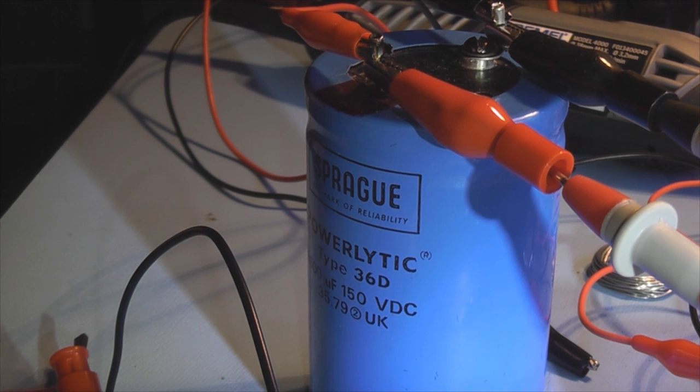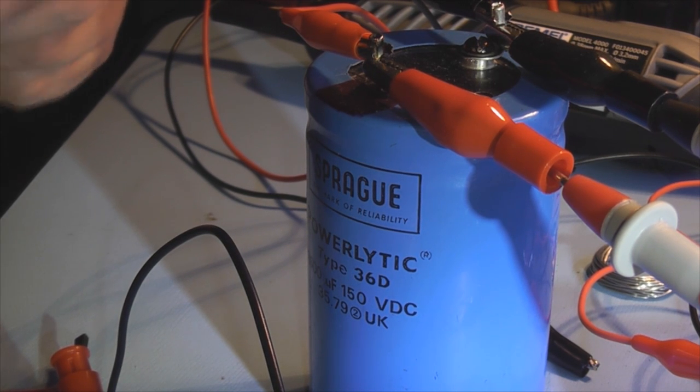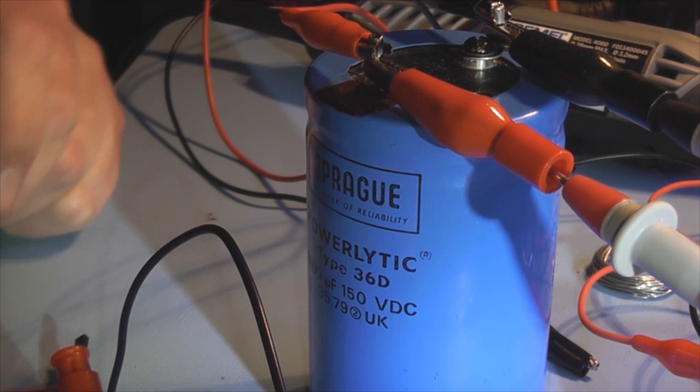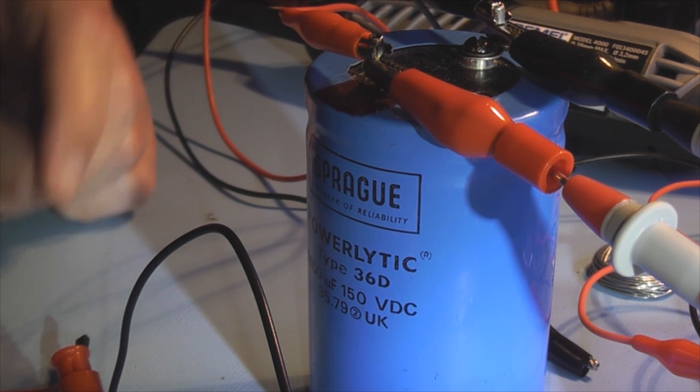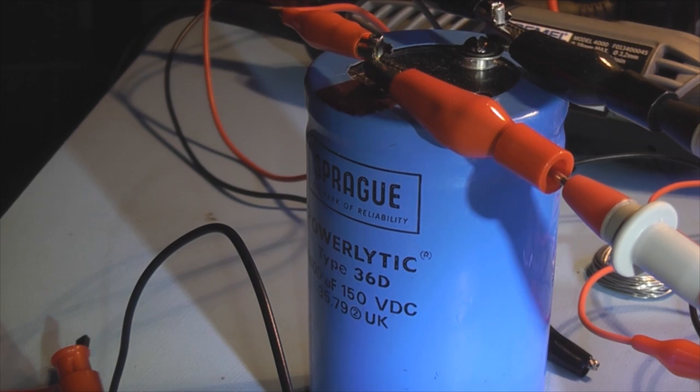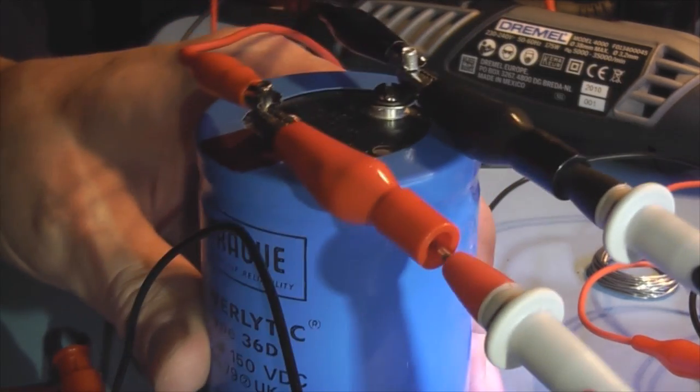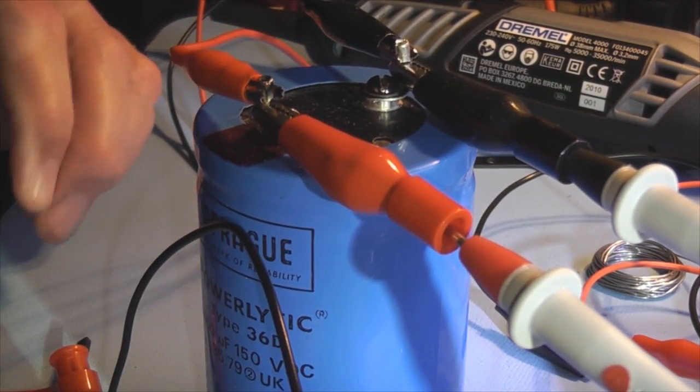Which in turn will cause less internal stress in the capacitor. Because a lot of capacitor damage is caused by the capacitor banks and things being arced out. The shock, the internal shock in the capacitor when it's arced out like that doesn't do them any good at all and will shorten their lives.